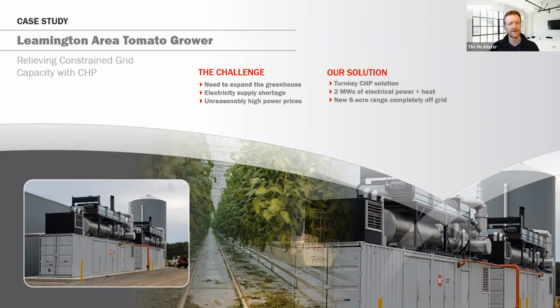I think it was commissioned around 2021 or 2022. We had an existing tomato grower with a large facility growing tomatoes for essentially 3 seasons of the year. They decided to build a new 6-acre range that would grow year round, with state-of-the-art technology, high efficiency lighting, and all the latest gadgets. While constructing this facility, they were not able to get the 2 megawatts of additional power capacity from the utility company to energize it. So they either had to scrap the plan, move it to another jurisdiction—which wouldn't be logistically feasible—or generate their own power.